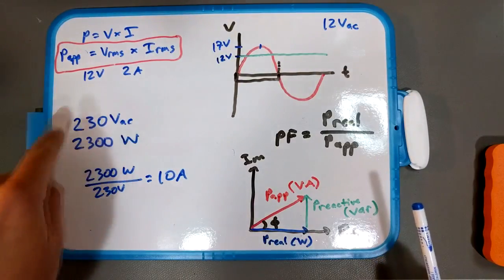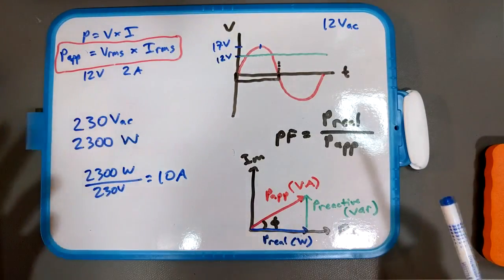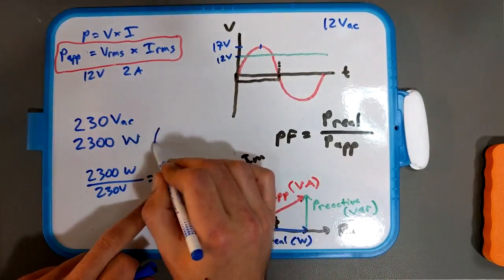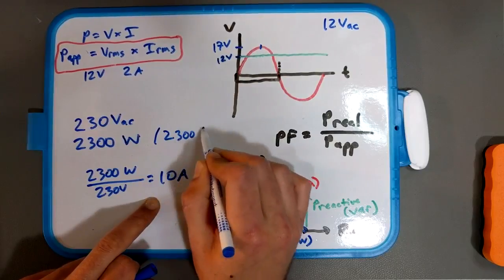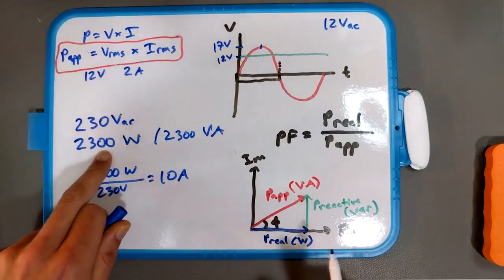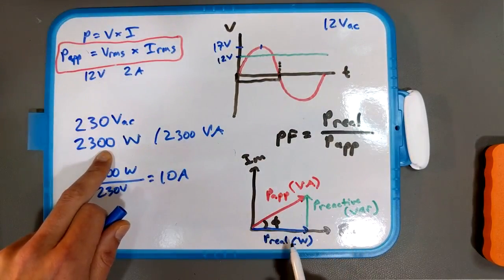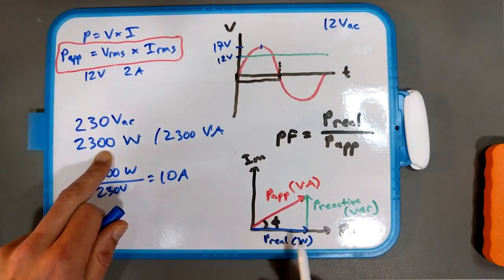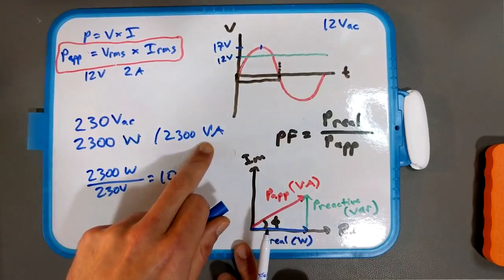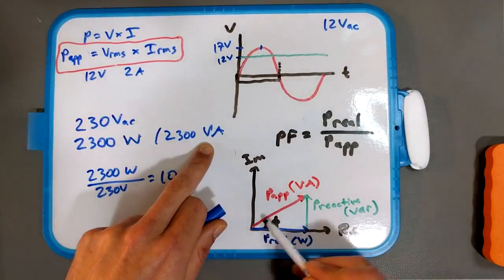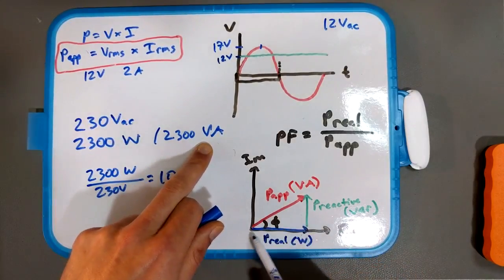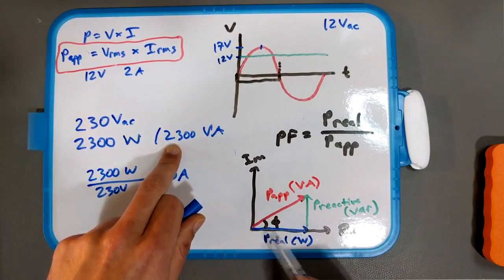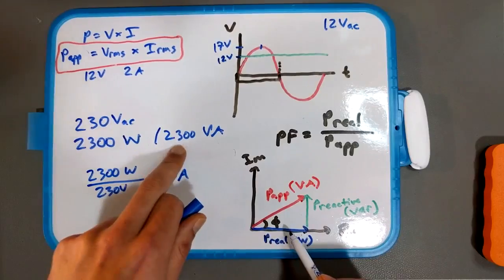But when you're looking at like nameplates to machines and stuff, it gets a little complicated, because it depends on do you see 2300 watts or do you see 2300 VA. If you see watts, that's referring to the real power, the power that you are actually being billed for, the power that your gizmo is consuming to do work. If you see 2300 VA, then that's this apparent power here. And the actual real power that your gizmo is using to do work is going to be less than 2300.